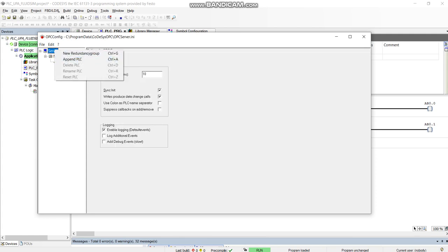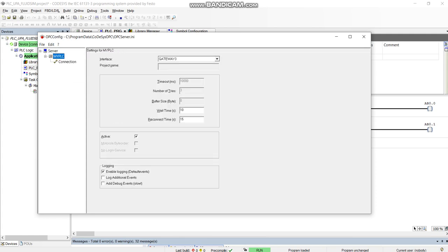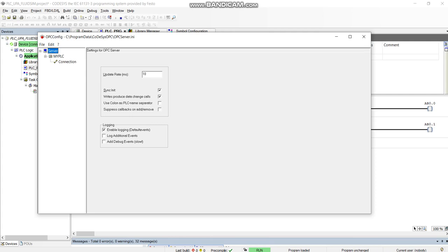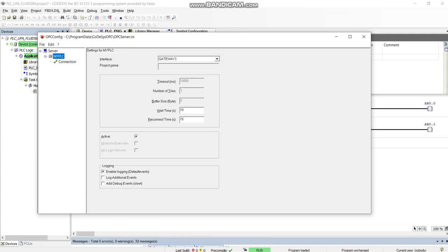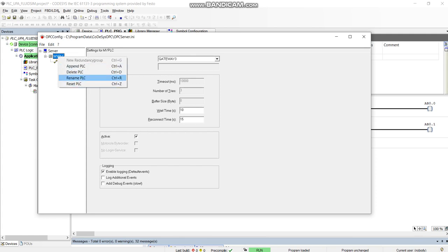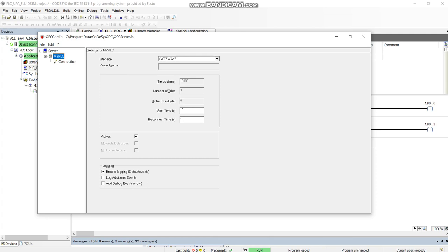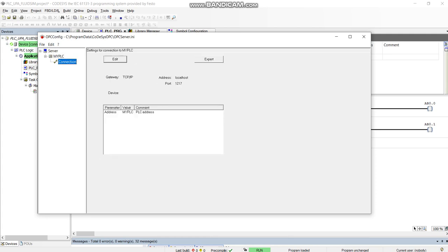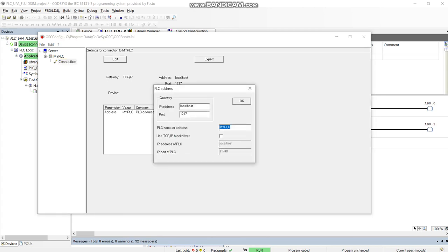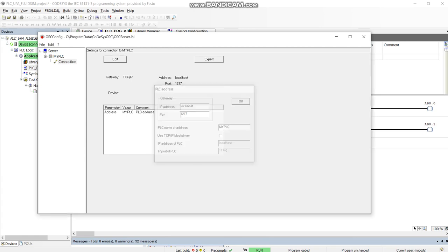I'll give you the PLC here. I've set my update rate to 10 milliseconds and tick these boxes and call it - so you can rename the PLC. So call it My PLC, make sure it's on Gateway 3, and then in the connection, again if you're going to edit here, you've got to make sure this is called My PLC as well and have these settings.